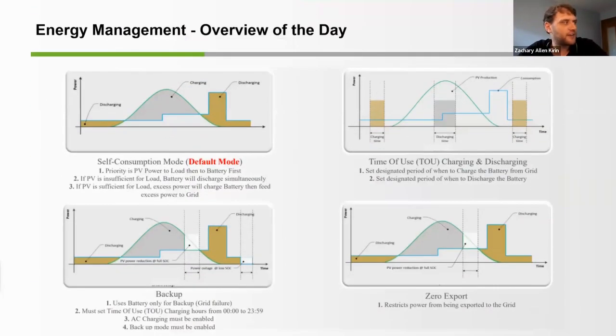So to put all this together, the self-consumption mode is the default mode. It's allowing that charging to occur to charge the battery, not export as much to the grid, and then discharge the battery for times when the customer needs. This is the self-consumption mode. We discussed the time of use charging and discharging. Again, the discharging is the most important. We can set the charging time as well. The battery can be set to charge either from the AC or strictly from the solar production.